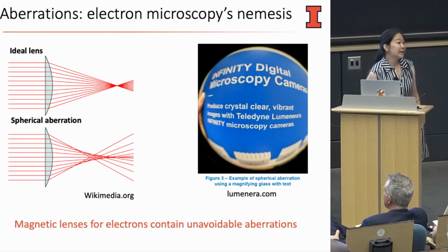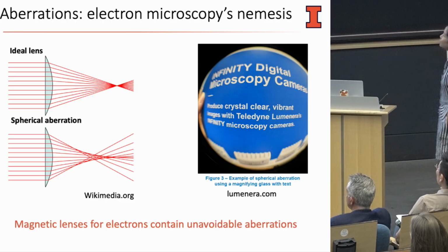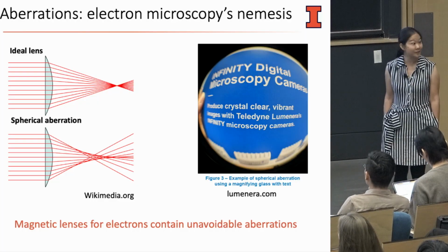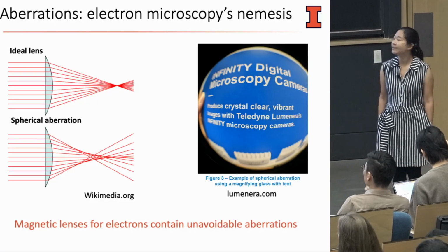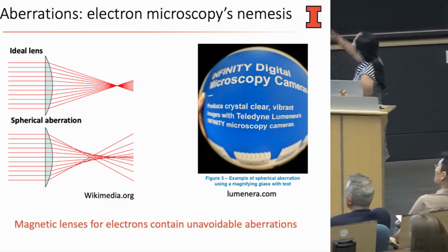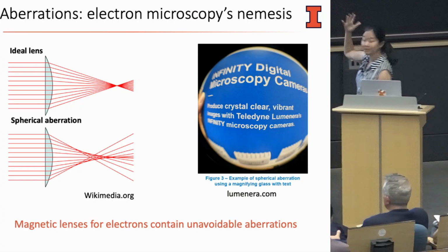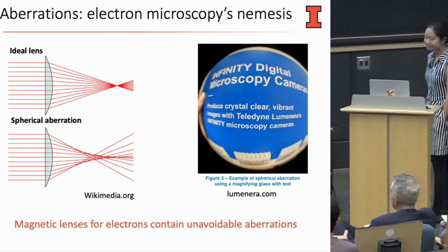And the thing that we're fighting is the fact that electron lenses are very bad. So we have aberrations. They are unfixable for electron optics because of Maxwell's equations. So that's fun. And really, the quality of lens that we're working with, a typical round lens, has aberrations that look like this. They're spherical aberrations. They're like looking through the bottom of a Coke bottle.